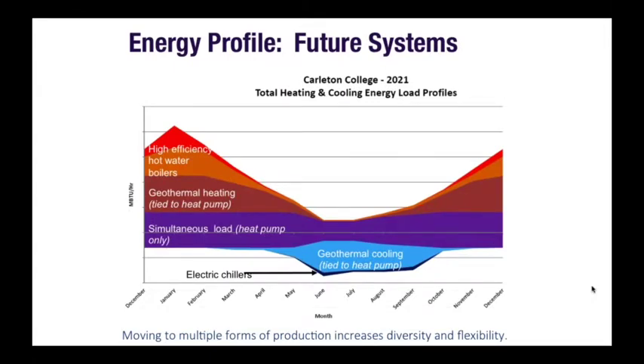We sized the geothermal system so that, for the middle range, we can take advantage of simultaneous heating and cooling, running that system almost continuously and using both sides of the output for the most efficient operation possible. We use the geothermal system for heating up to a certain size, then hot water boilers for heating above that for peak loads. Similarly, on the cooling side, we run the geothermal system for cooling, and beyond the load where it's efficient to operate, small chillers take over that peaking. These also give us redundancy, which we need in Minnesota and anywhere heating and cooling are really required.